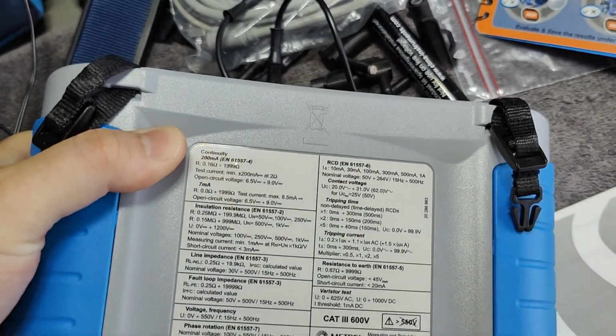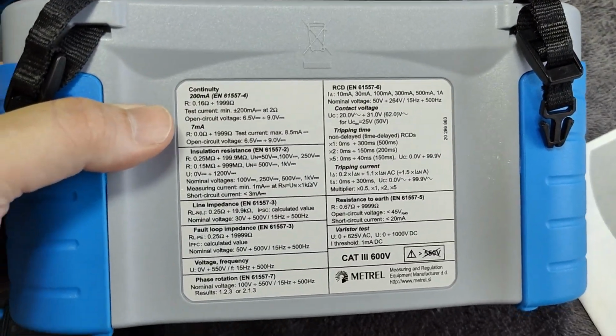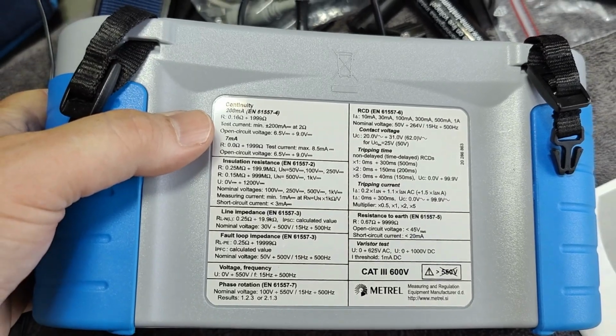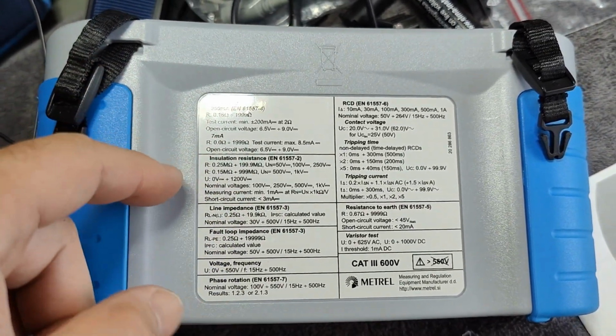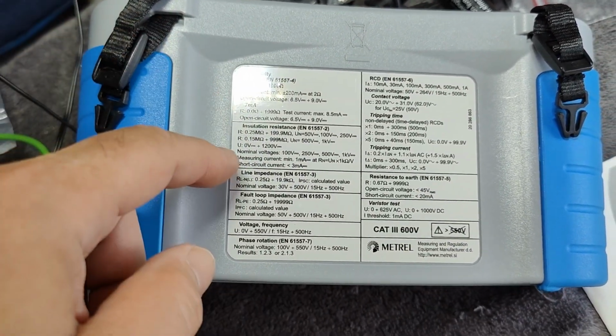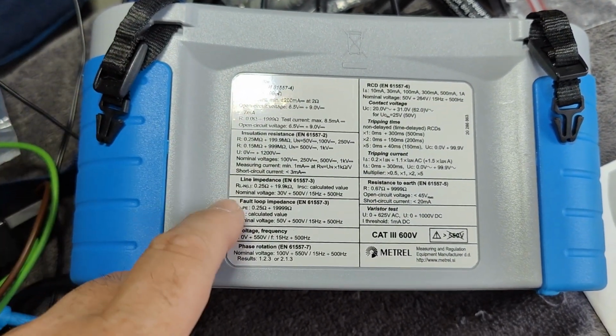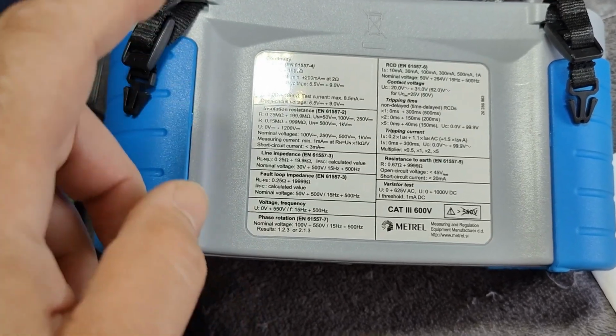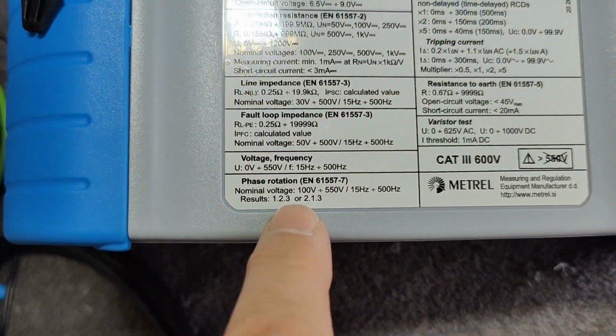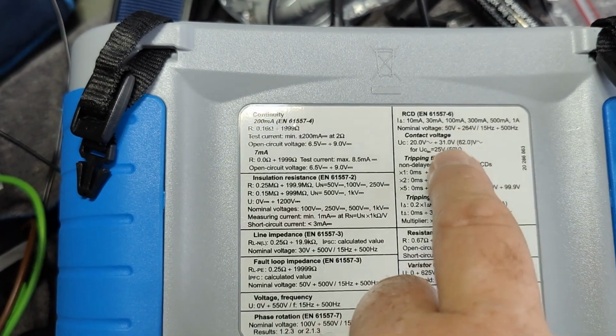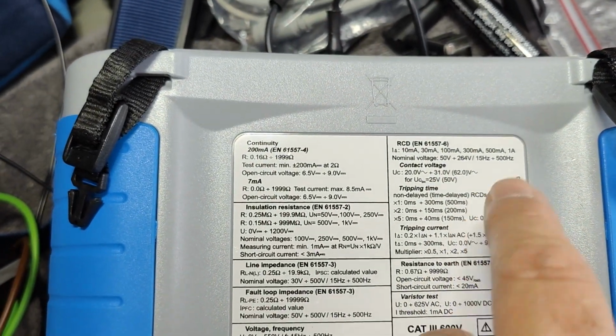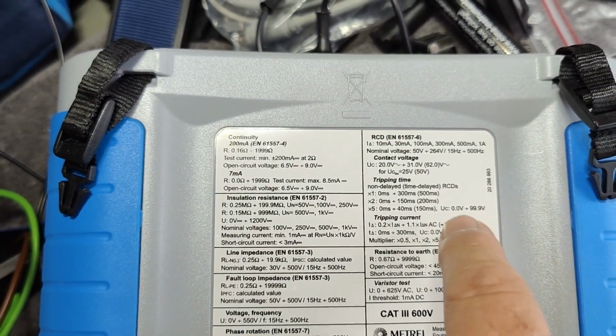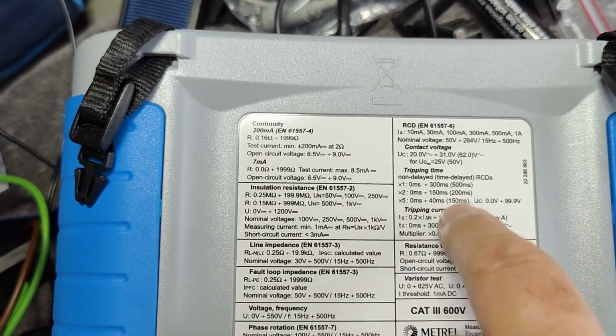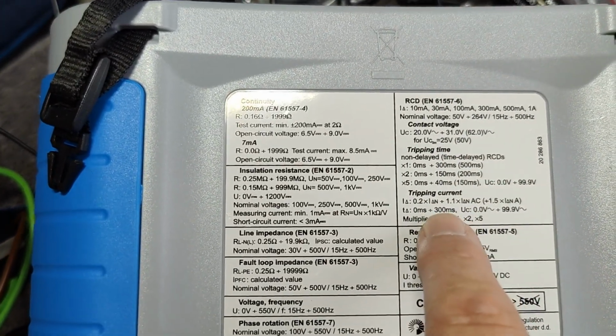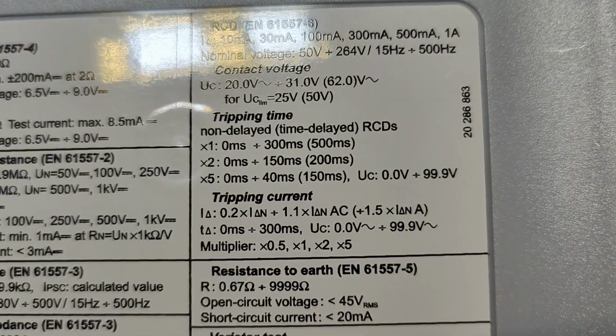I believe this thing can do all the things you need for your home or building facility: test insulation, line impedance, fault loop, voltage, frequency, phase rotation. It can test your protection relay, your leakage protection relay, the trip time and trip current as well.